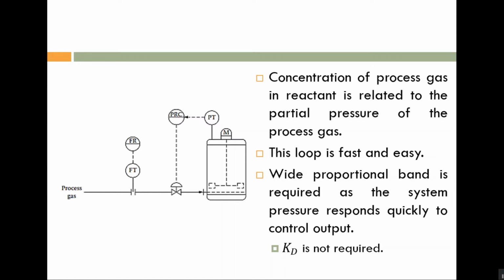Okay, so here you can see that we are controlling pressure by manipulating the flow rate of process gas. Two things are there here. First, the speed of response of pressure is very large compared to temperature. Temperature is the slowest variable. Pressure is a relatively high speed variable. And it is manipulating the process gas flow rate also. You can see that the range of flow rate of gas and the range of flow rate of liquid are entirely different.